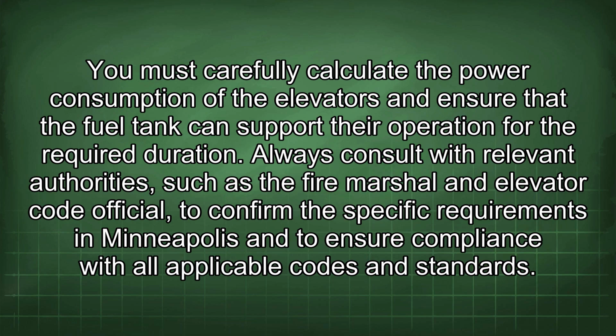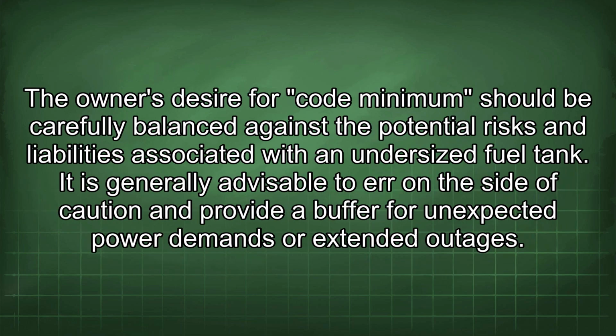Always consult with relevant authorities, such as the fire marshal and elevator code official, to confirm the specific requirements in Minneapolis and to ensure compliance with all applicable codes and standards. The owner's desire for code minimum should be carefully balanced against the potential risks and liabilities associated with an undersized fuel tank.